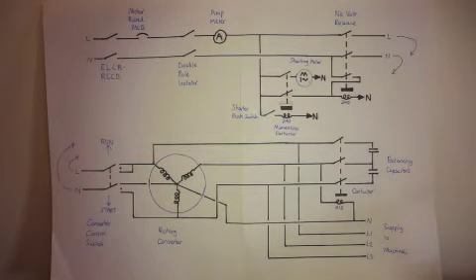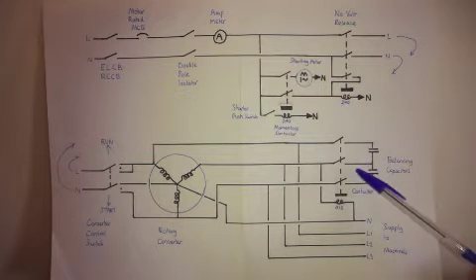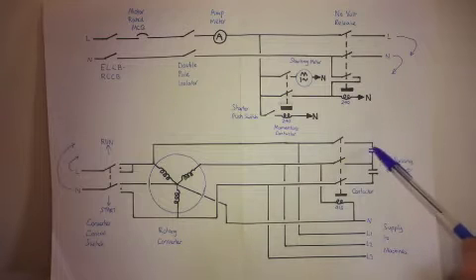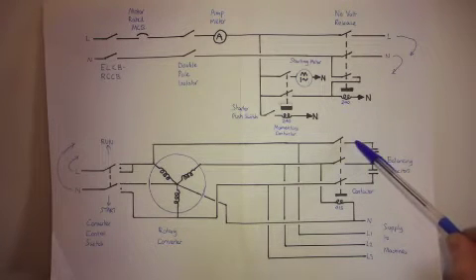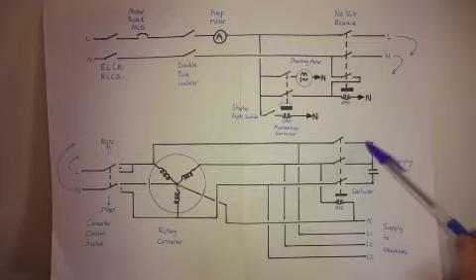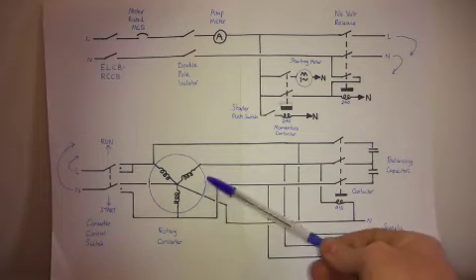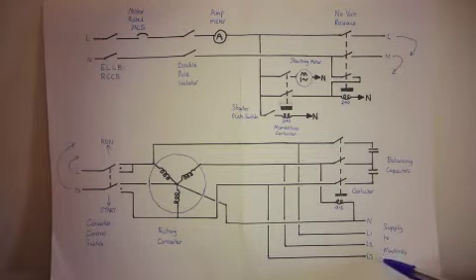You may find that you have to do differently, but what is important is that you check your currents and voltages of each phase at every stage. In the general rule, putting increased capacitance will increase the voltage of the phase and therefore the current, but in this converter where you have two false phases, that's not always what's happening and it's a line of best fit.